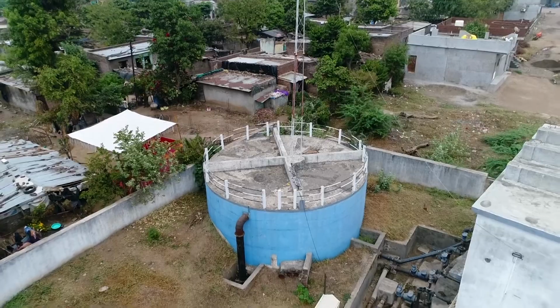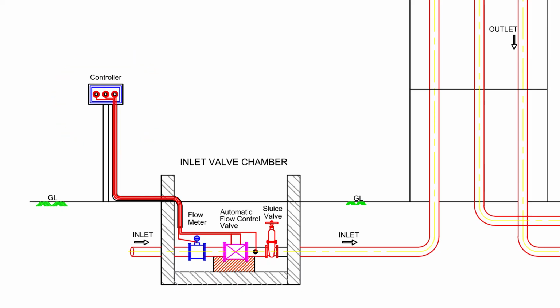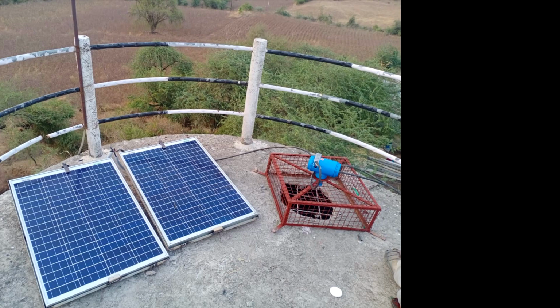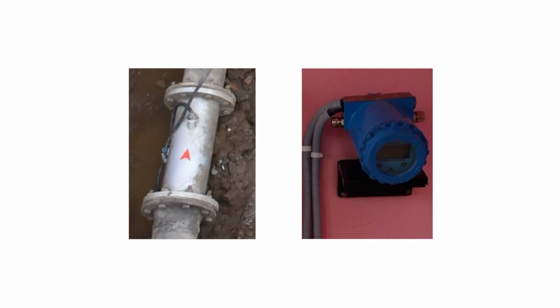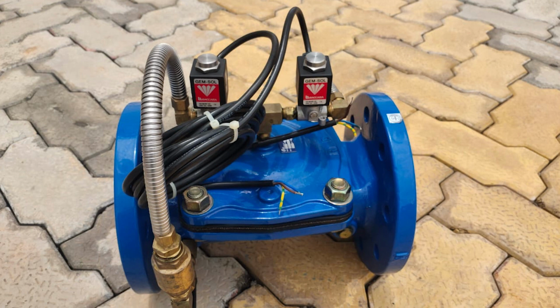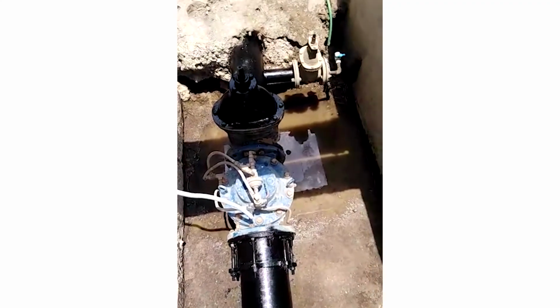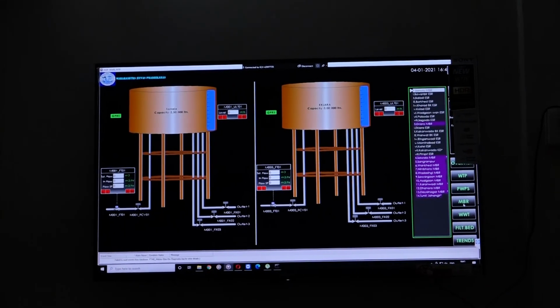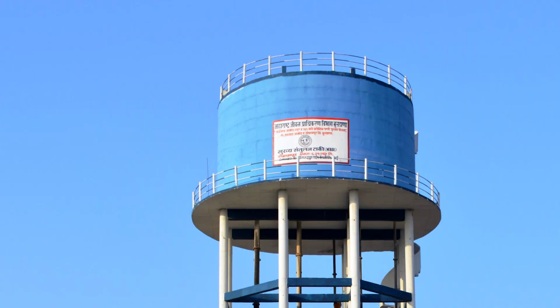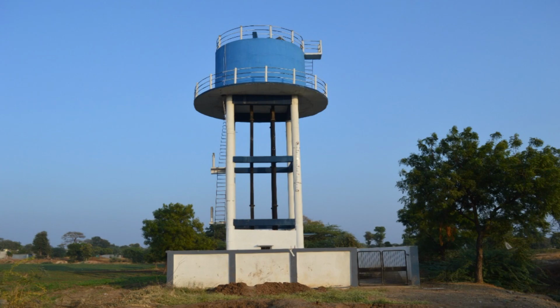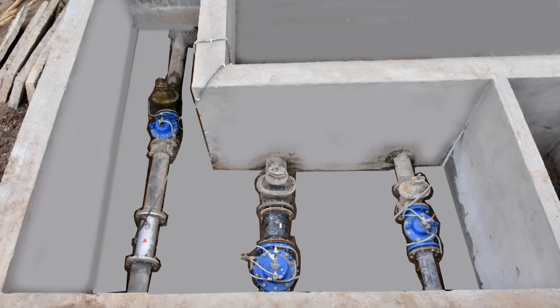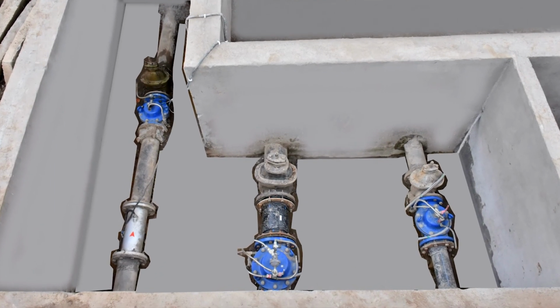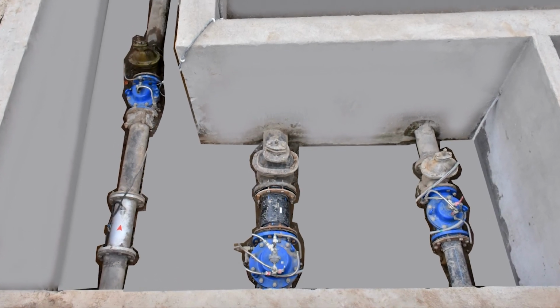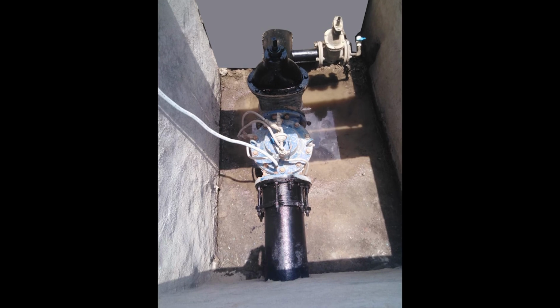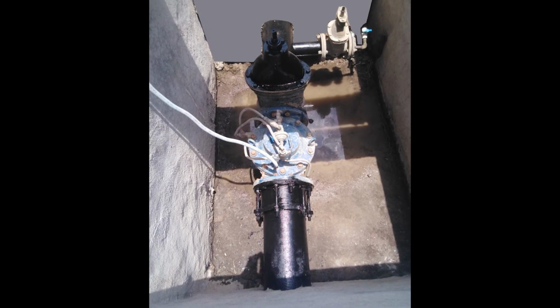Each MBR, GSR and ESR has a microprocessor controller along with ultrasonic level transmitters, a solar panel and battery backup, an ultrasonic flow meter, an automatic flow control valve at the inlet and an automatic on-off valve at the outlet. By monitoring the data, the operations can be controlled remotely from the master control room at the WTP. When the water level in the MBR, GSR and ESR reaches its designated mark, the intake flow of water gets regulated by the flow control valve and it gets shut off gradually, thereby avoiding the overflow of water and eliminating the probability of water hammer in the feeder mains.